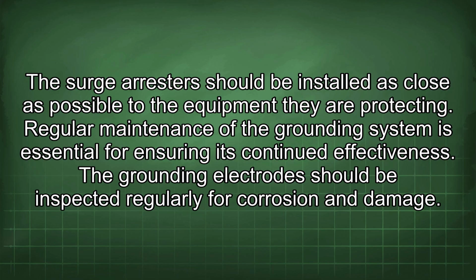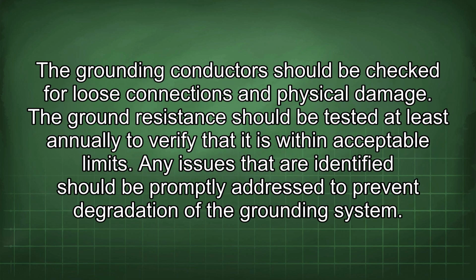Regular maintenance of the grounding system is essential for ensuring its continued effectiveness. The grounding electrode should be inspected regularly for corrosion and damage. The grounding conductors should be checked for loose connections and physical damage. The ground resistance should be tested at least annually to verify that it is within acceptable limits. Any issues that are identified should be promptly addressed to prevent degradation of the grounding system.